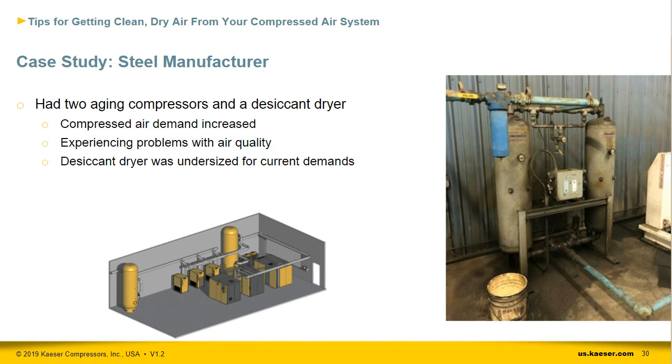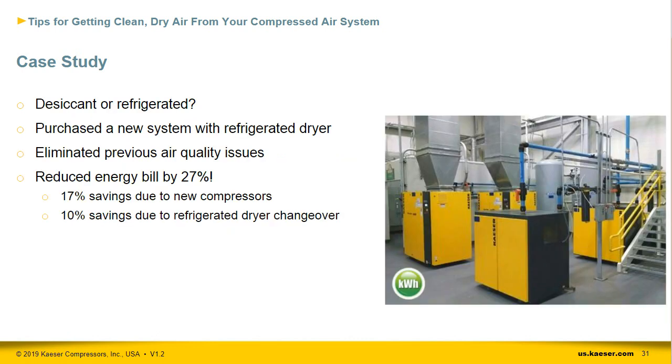The customer ultimately decided to perform an energy audit on his compressed air station, and in doing so, it was determined that his existing desiccant dryer was undersized for the current plant demands. Knowing that a new dryer would be necessary, the energy audit touched on the topic of required air quality and helped to break down the cost of desiccant quality air versus the air quality provided by a refrigerated dryer. The customer evaluated his application and, with help from his team and the energy audit, determined that desiccant quality air wasn't required for his process.